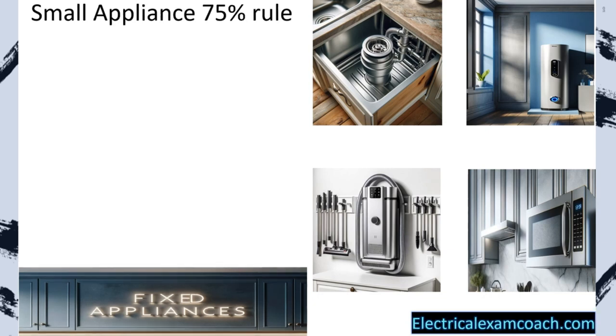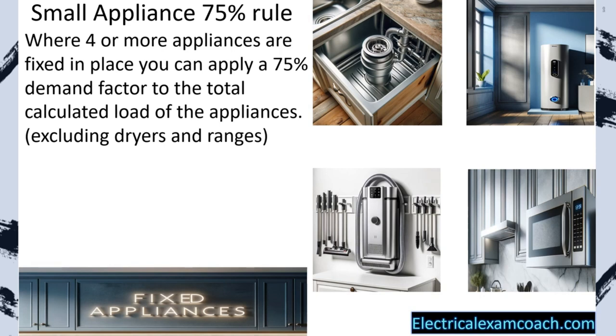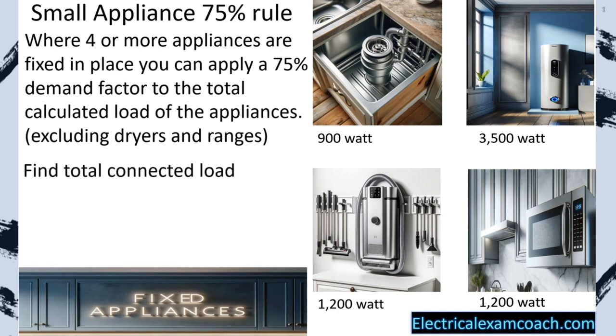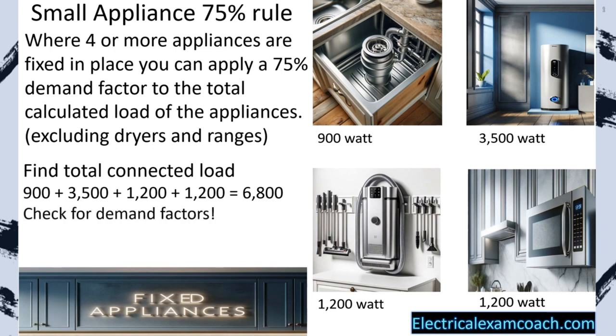The small appliance 75% rule works like this: where four or more appliances are fixed in place, you can apply a 75% demand factor to the total calculated load of the appliances. This excludes dryers and ranges — we'll calculate those separately. Let's imagine we have several appliances totaling 6,800 VAs. First, find the total connected load: 6,800. Then check for demand factors — we apply the 75% rule: 6,800 multiplied by 0.75 gives us a new reduced load of 5,100 watts, and that's what we add to our whole-home load calculation.